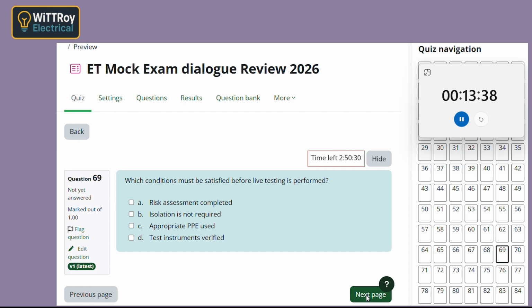Yeah, I wasn't too sure about that one. That's fair. You only do live testing when it's necessary, and when you do, you make sure everything is controlled. So you check the risks, wear the right PPE, and make sure your test gear is working properly. So it's not like skipping safety steps. Exactly. That option saying isolation is not required, that's not the right mindset. Isolation is always preferred unless you have a good reason not to.